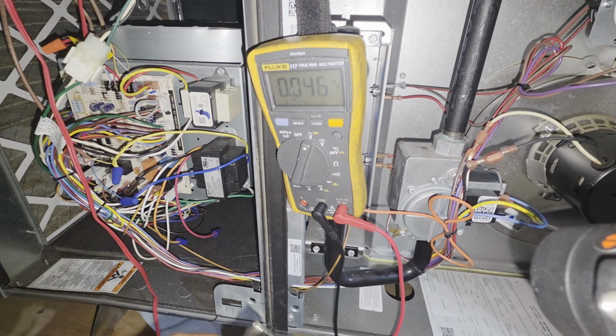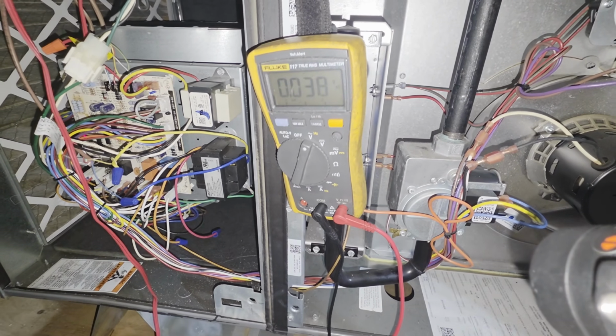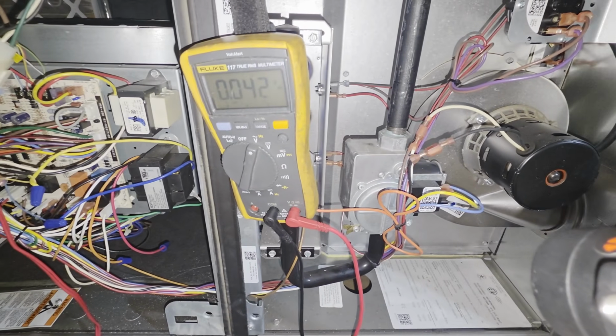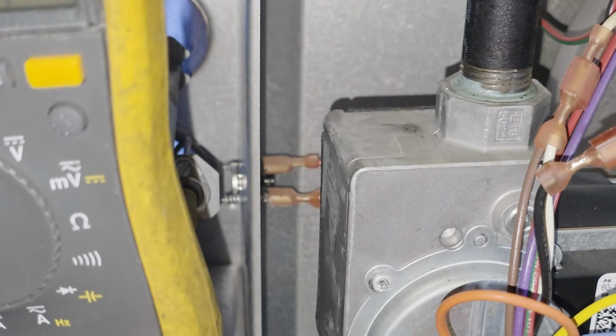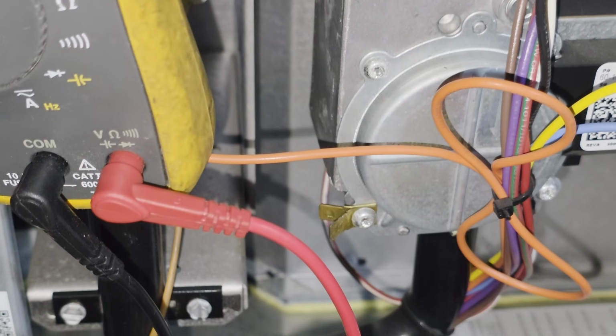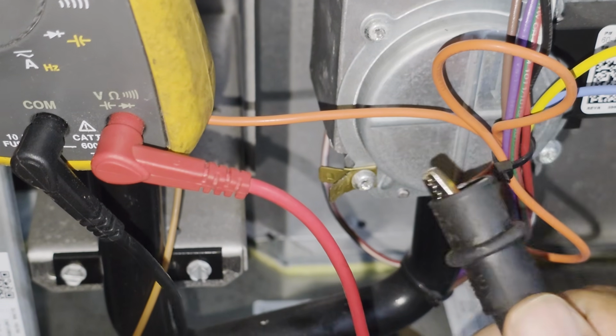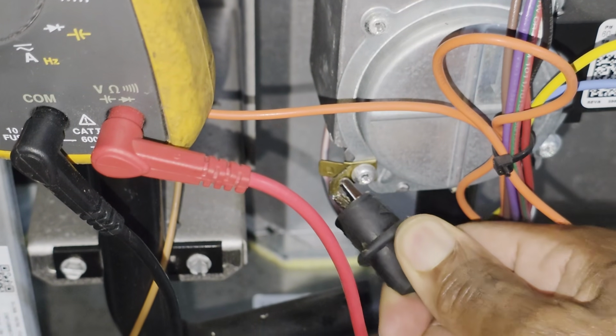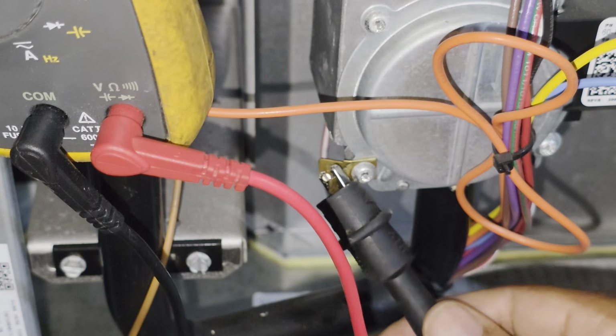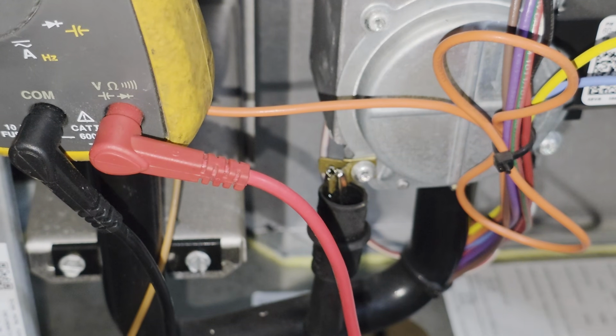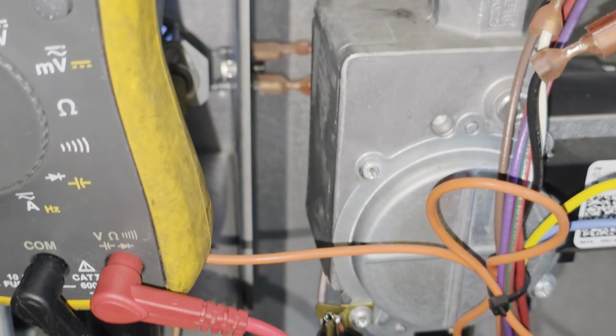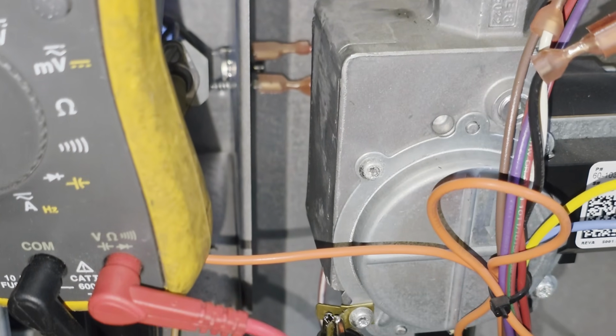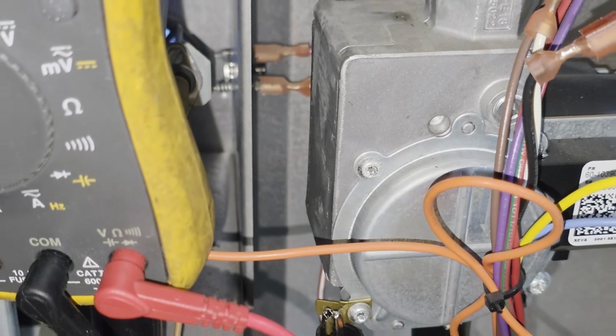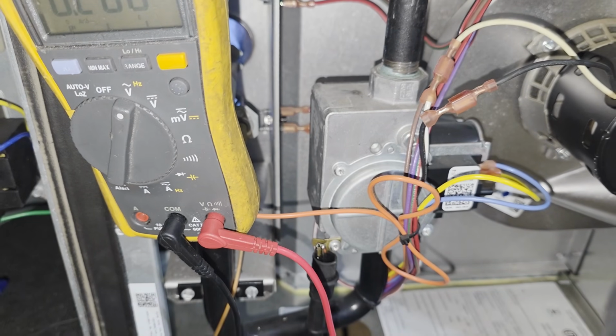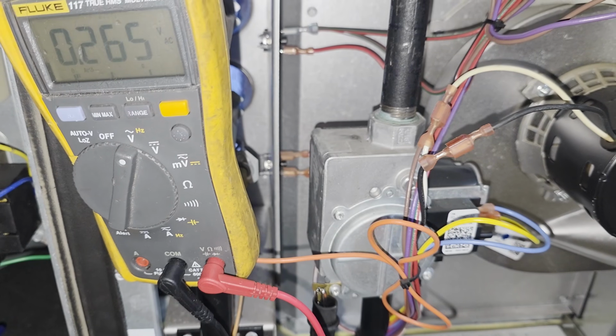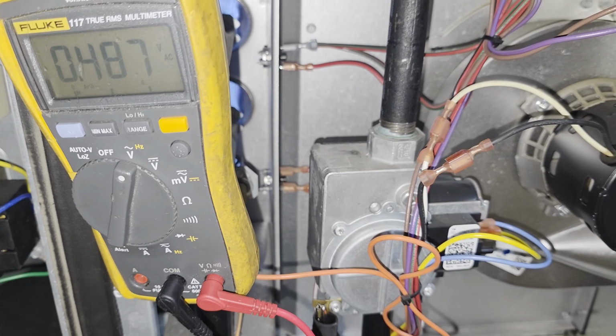And that's common. You see this neutral right here? I even think they make the terminals on that gas valve. That's a good ground right there. See if you see the terminal. See it? That's a good ground. And I think that's why they make it, it's like a little terminal. But that's a good pivot right there. And we're doing the same thing. Just go to your terminal. Got that good pivot. And back up a little bit so you see the meter too. Got us a good pivot right there on that ground.